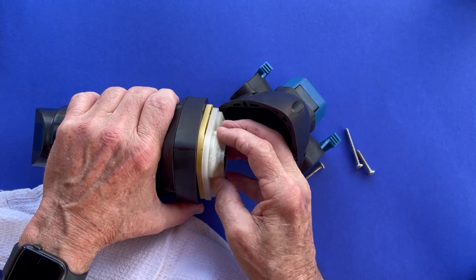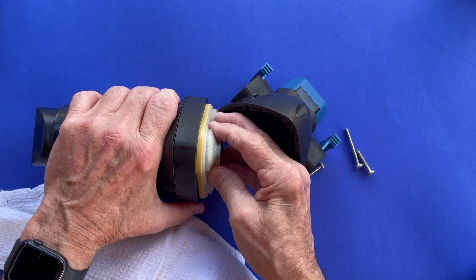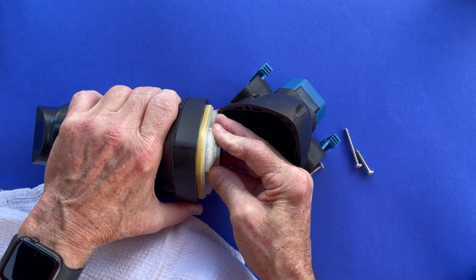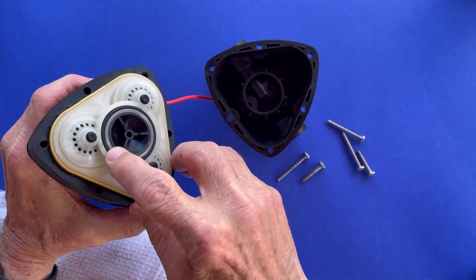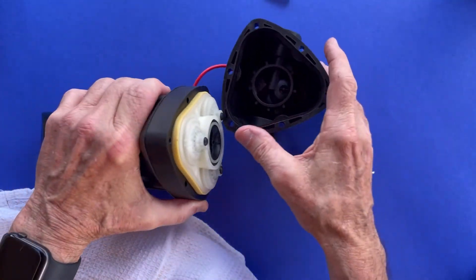Now take the new Viton valve block and drop it in place. Make sure it seats properly in the wobble plate seal. Also make sure the o-ring in the top of the valve block is seated properly.